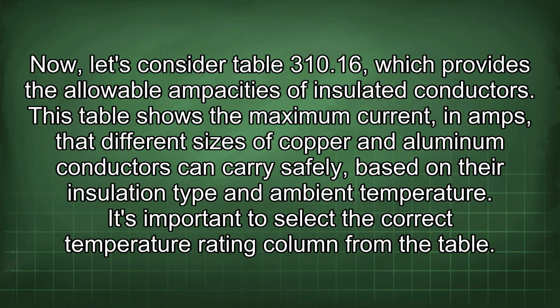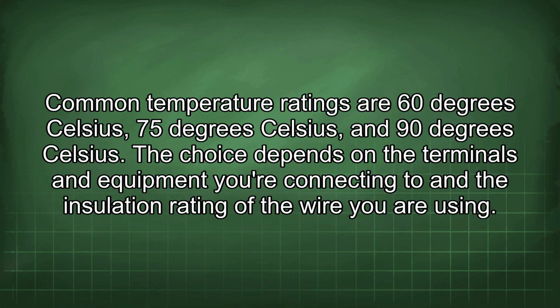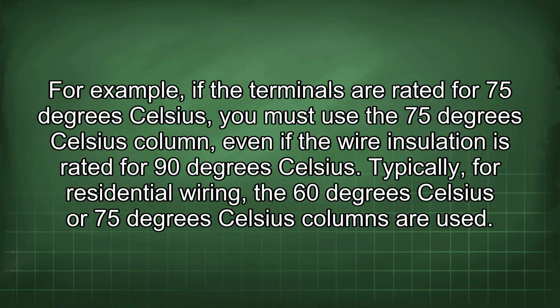It's important to select the correct temperature rating column from the table. Common temperature ratings are 60 degrees Celsius, 75 degrees Celsius, and 90 degrees Celsius. The choice depends on the terminals and equipment you're connecting to and the insulation rating of the wire you are using. For example, if the terminals are rated for 75 degrees Celsius, you must use the 75 degrees Celsius column, even if the wire insulation is rated for 90 degrees Celsius.